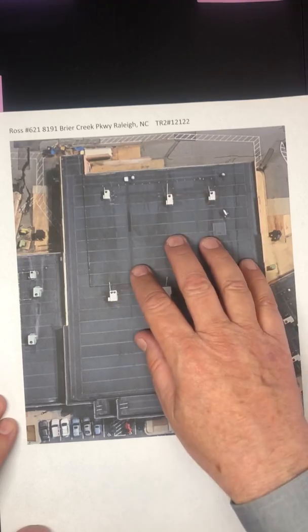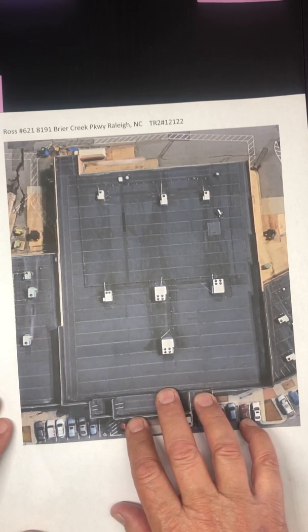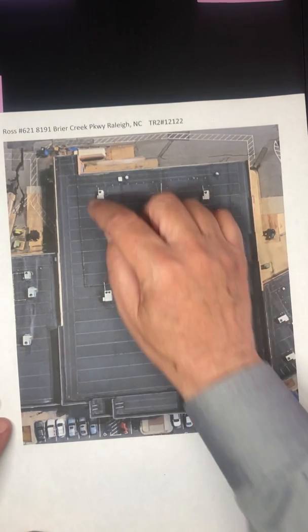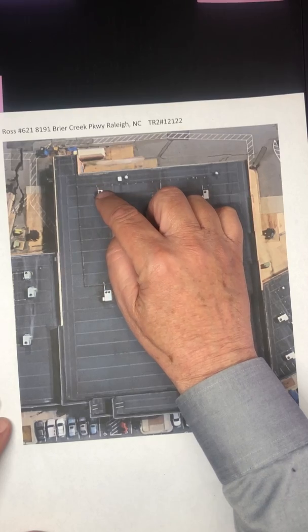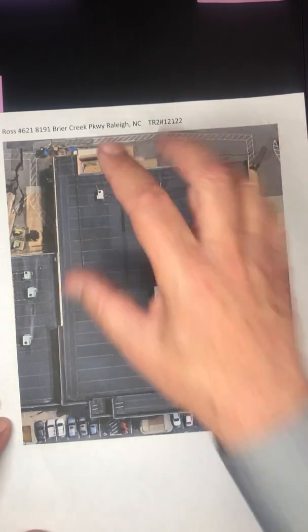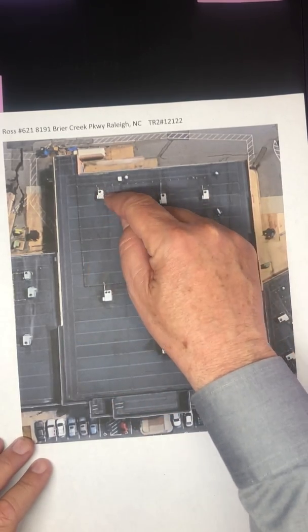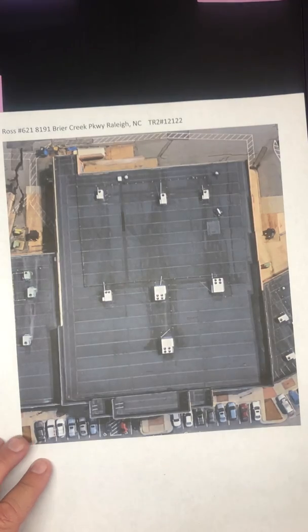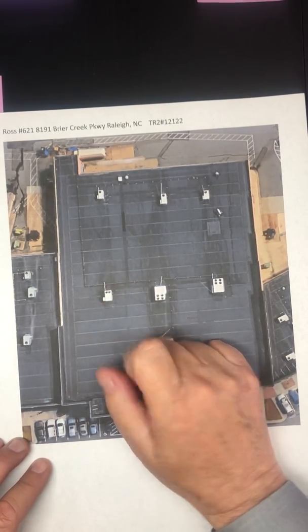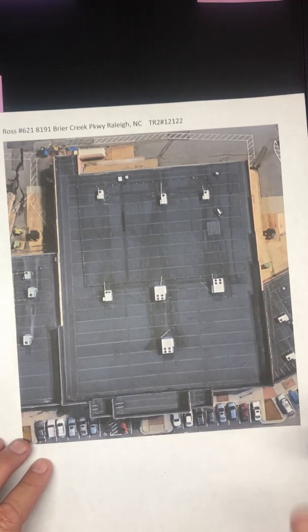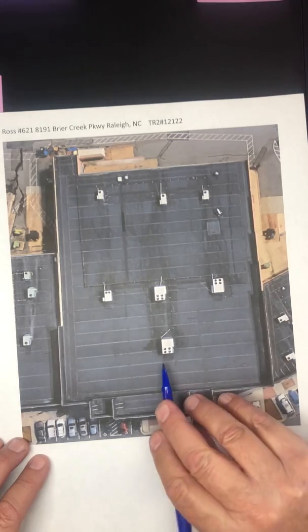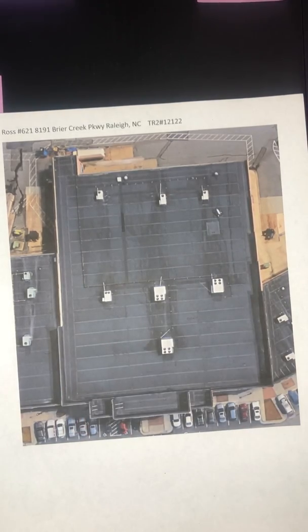One is I got to get the dimension, the location of all these units, both in the, say, left-right direction and the up and down direction. I need to get the dimensions of the curb, the RTU curb that it's sitting on top of. The unit sits on a curb, which is on the roof. And that curb is going to have an up and down dimension, a left and right dimension. Then I need to get the actual RTU numbers so I can identify which one is which. And then get photos. I'm looking for 4 photos, one from each direction of each of those units.